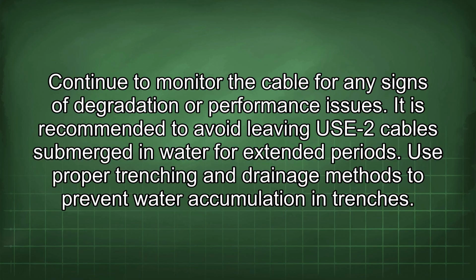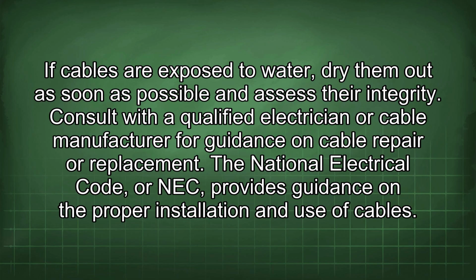It is recommended to avoid leaving USE-2 cables submerged in water for extended periods. Use proper trenching and drainage methods to prevent water accumulation in trenches. If cables are exposed to water, dry them out as soon as possible and assess their integrity. Consult with a qualified electrician or cable manufacturer for guidance on cable repair or replacement.